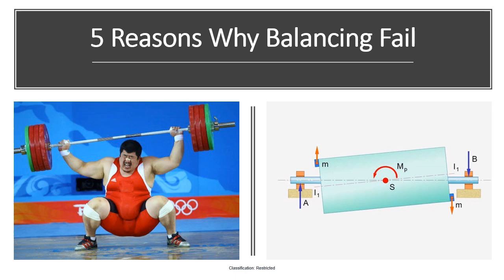Hello everyone, welcome to this video. Today I'm going to talk about the five main reasons why our balancing attempt will fail in the field and how to avoid them. It is important because studies show the power loss due to unbalance is 0.11 watt per gram-mm of unbalance, and unbalance is up to 50% more destructive to bearing life than other vibration sources producing equal vibration levels.